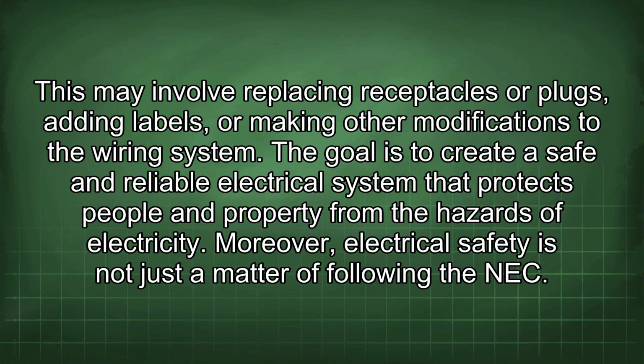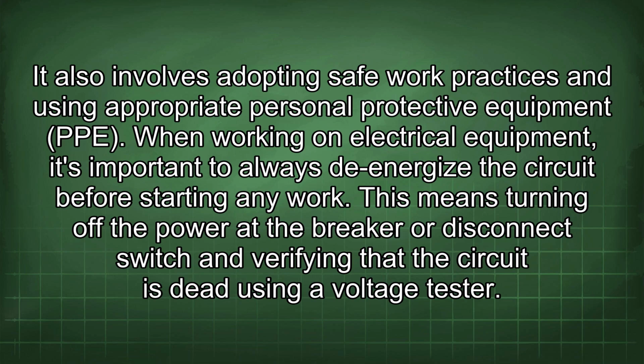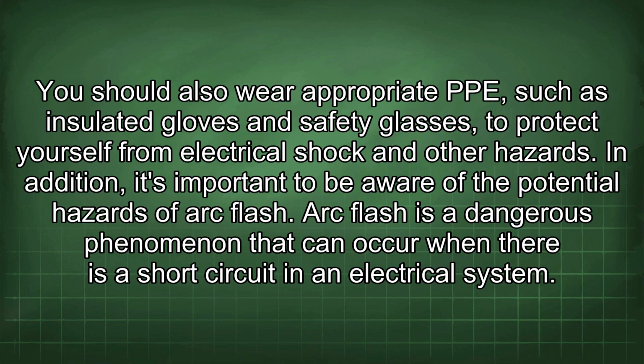Moreover, electrical safety is not just a matter of following the NEC. It also involves adopting safe work practices and using appropriate personal protective equipment (PPE). When working on electrical equipment, it's important to always de-energize the circuit before starting any work. This means turning off the power at the breaker or disconnect switch and verifying that the circuit is dead using a voltage tester. You should also wear appropriate PPE such as insulated gloves and safety glasses to protect yourself from electrical shock and other hazards.